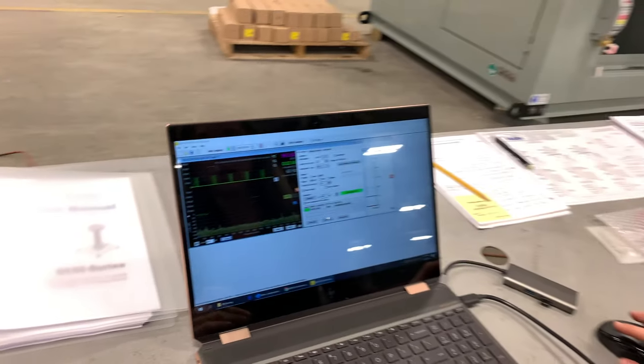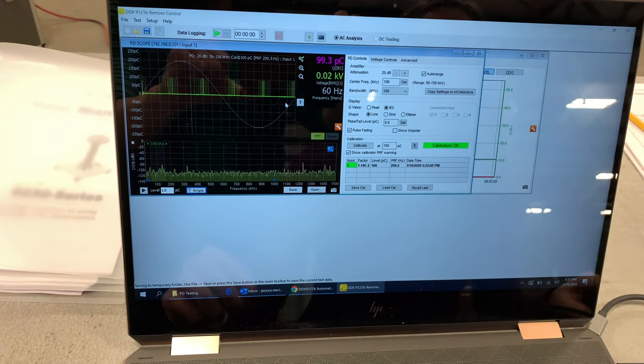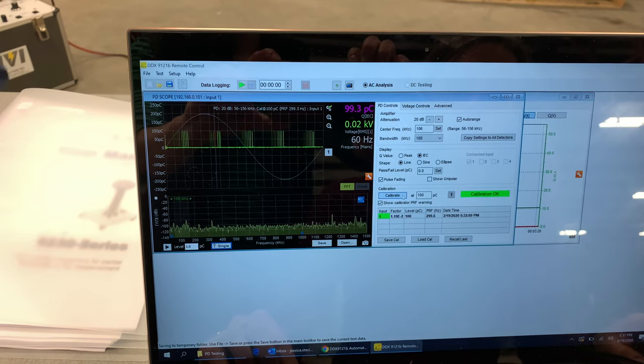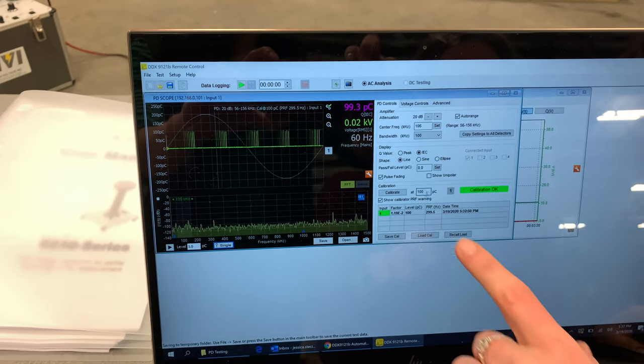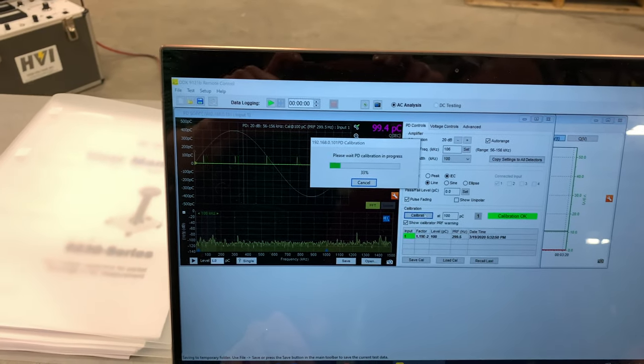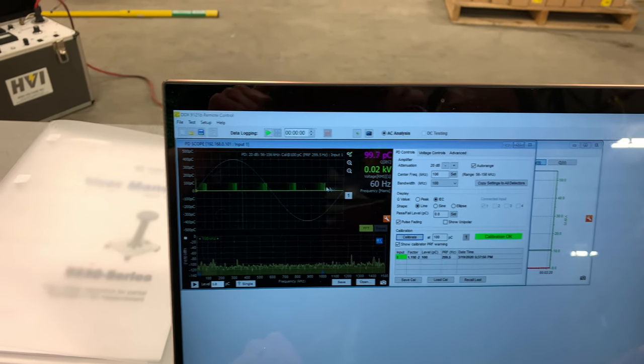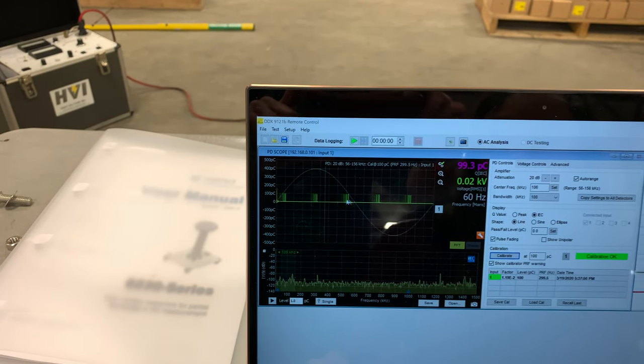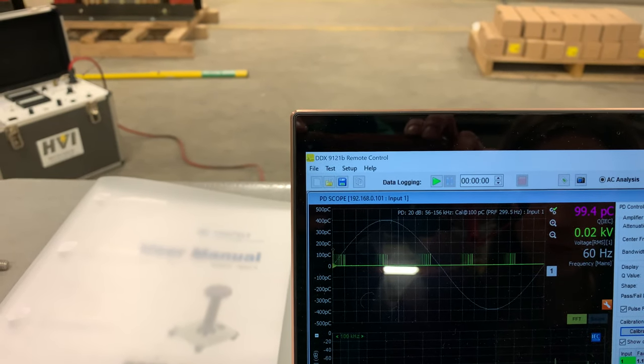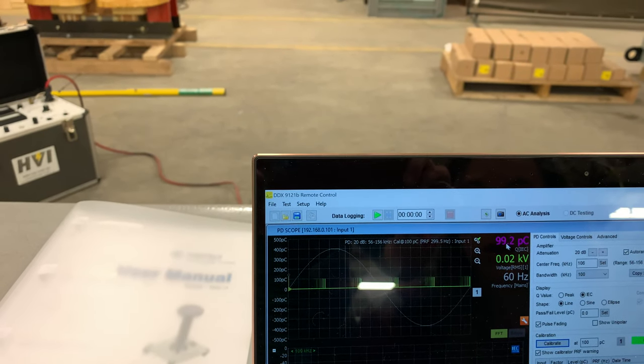Hello everybody. I'm working with the DDX 9121B remote control — this is the software that came with the PD detector. As Paul said, he just connected the calibration to the coupling capacitors. I set it to 100 picocoulombs, because that's what he set the other device to, and hit calibrate. That simply calibrates what is being read by the PD detector. Here is a graph showing the picocoulombs being read — there's 100 picocoulombs, right where all the signal spikes are. So it is calibrated.